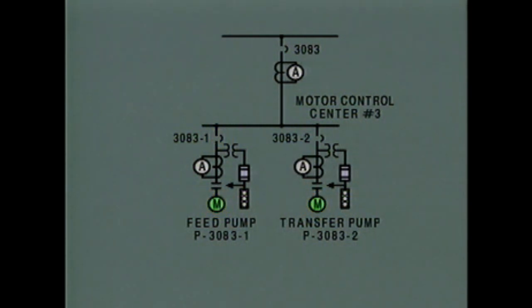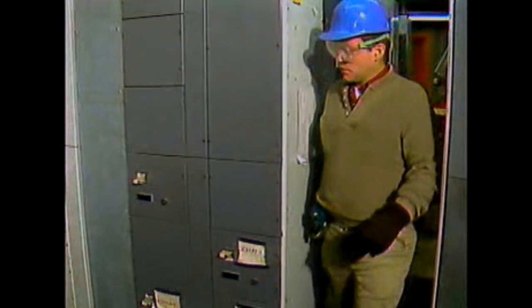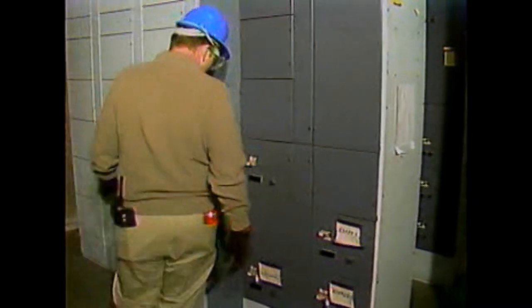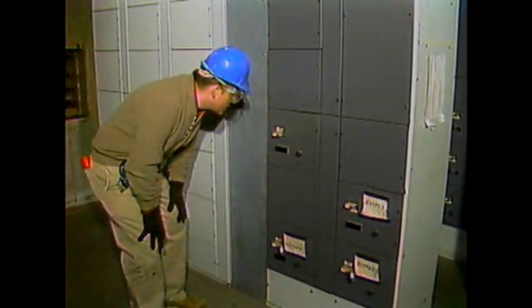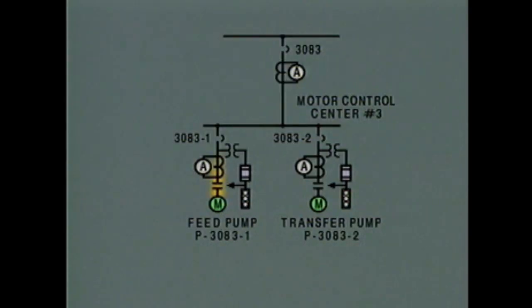In many cases, components represented on an electrical one-line diagram are numbered. The diagram we've been working with shows how component numbers may appear on a diagram. You can use the ID numbers to verify that you've found the right component by matching the number on the diagram with the number on the component in the plant. In our example, the system diagram helped us isolate one component without disturbing the rest of the system. By tracing the power path back from a component, we can find the breaker that's used to isolate the component from its power source.